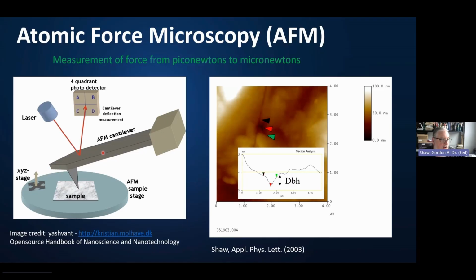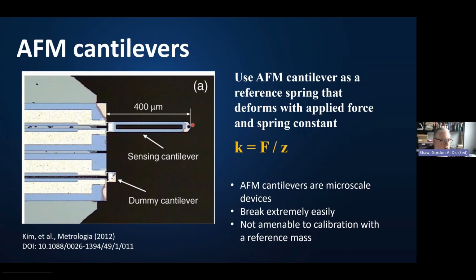Typically, the probe that is used in atomic force microscopy is an AFM cantilever, and I have a picture of one here. You can see it's about 400 micrometers in length in this case. It is microfabricated typically from silicon, and it's treated as a spring, so it follows Hooke's law. If you can measure an applied force and you can measure the displacement of the cantilever as it bends, you can calculate a spring constant, which I call K here. This K can then be used as a way to measure the force if we can measure the bending of the cantilever beam. Unfortunately, these are very small, they break very easily, and so you cannot use a reference mass to calibrate these cantilevers.